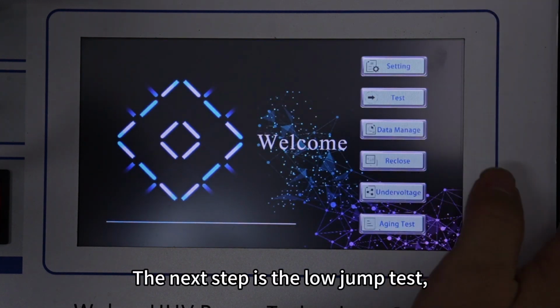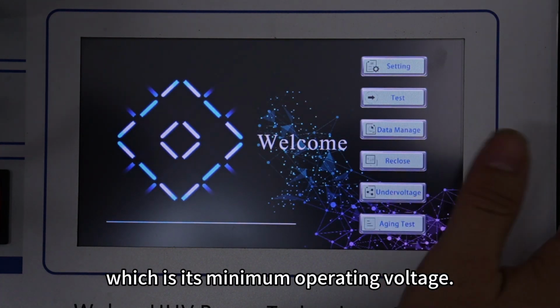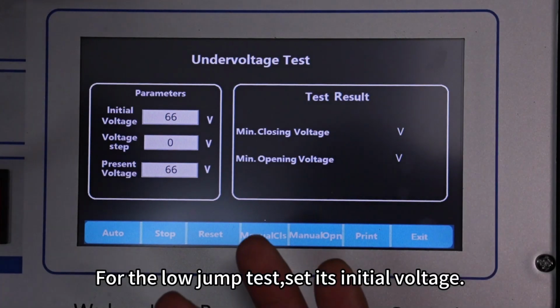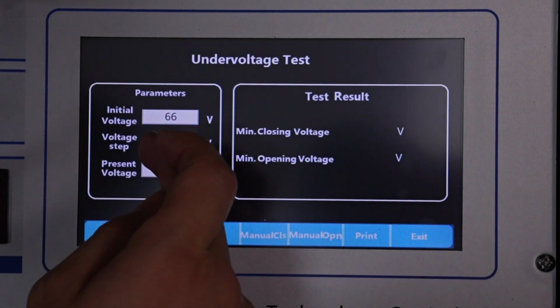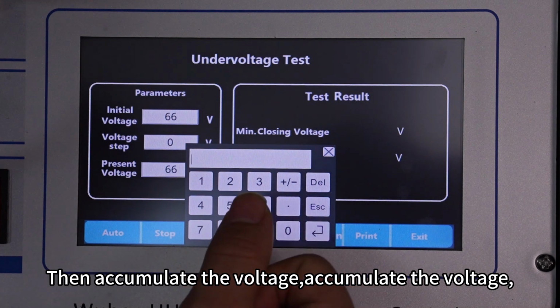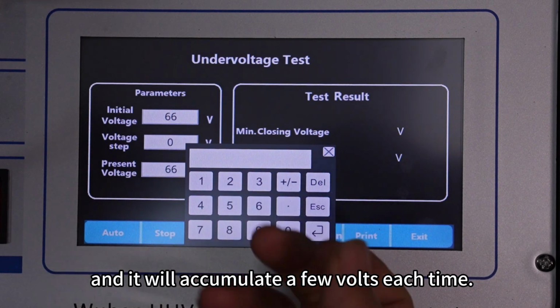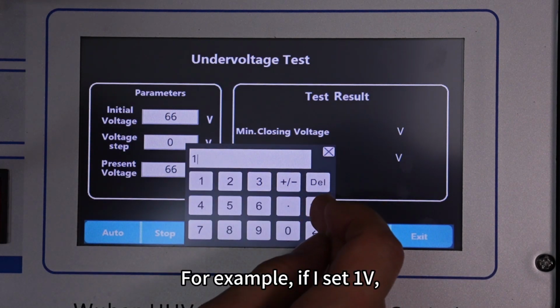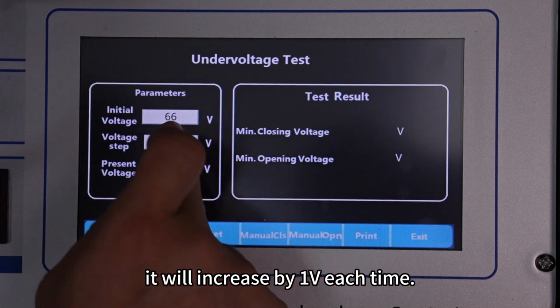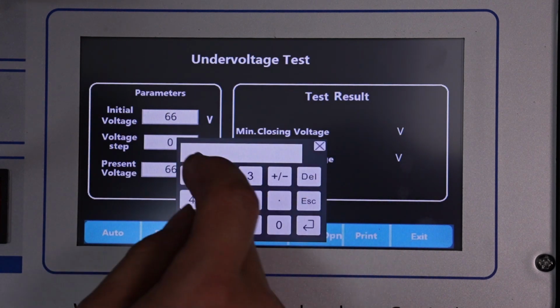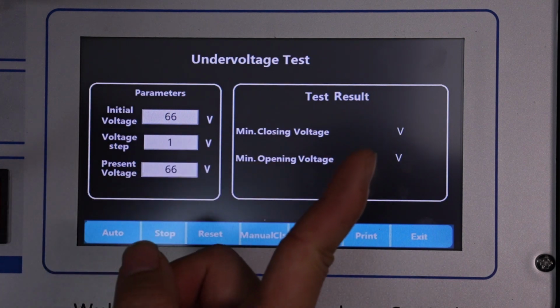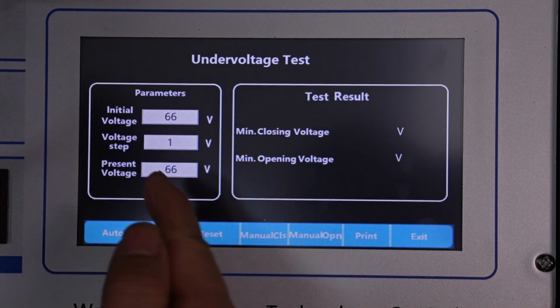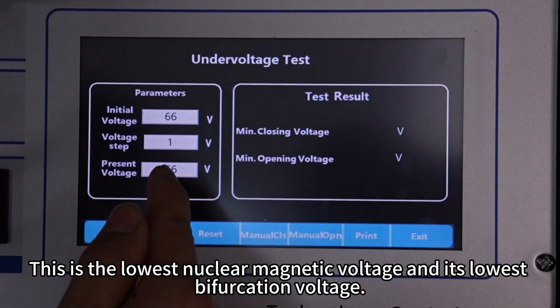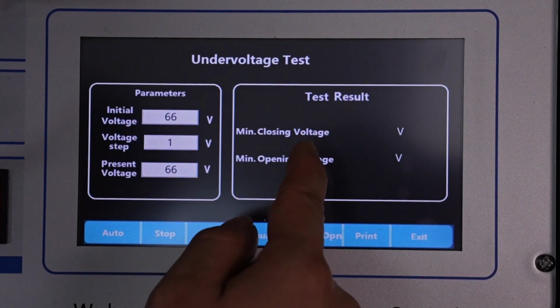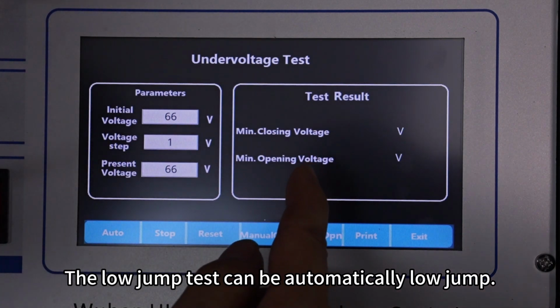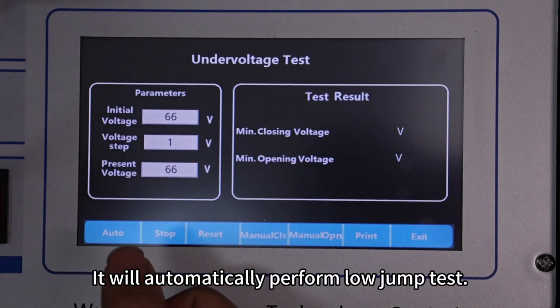The next step is the low jump test, which is its minimum operating voltage. For the low jump test, set its initial voltage. Then accumulate the voltage, and it will accumulate a few volts each time. For example, if I set 1 volt, it will increase by 1 volt each time. This is the current voltage. This is the lowest closing voltage and its lowest opening voltage. The low jump test can be automatically performed.